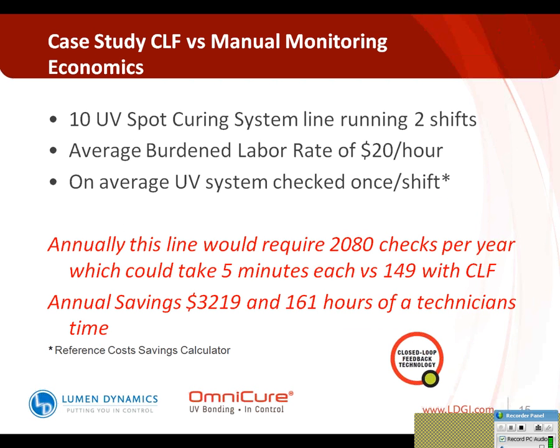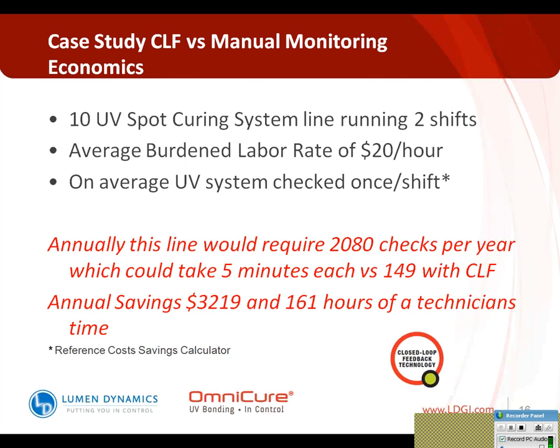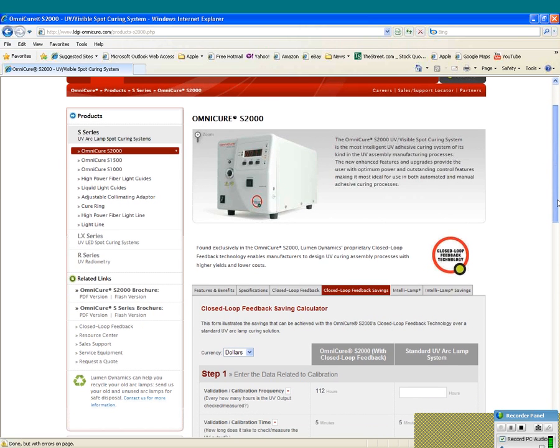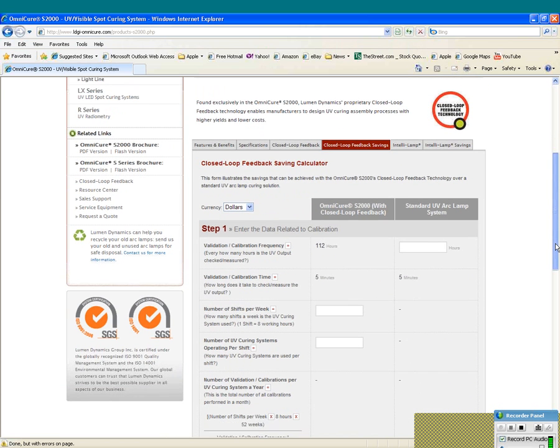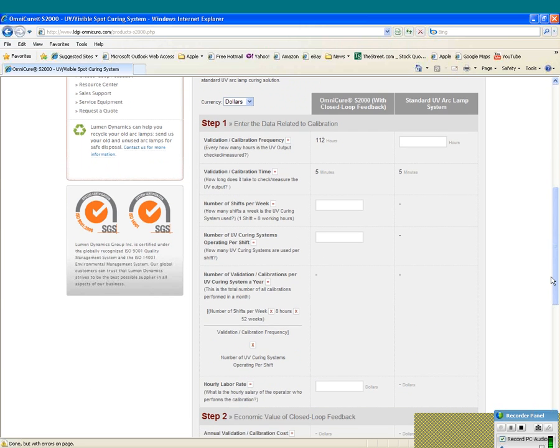So what I wanted to do is run a little calculation just to show you some of the potential savings that you can have with this calculator. The calculator here compares an S2000 system with a standard system that would have a manual adjustment. And in that particular system, what we're saying is that the system will maintain that output within plus or minus 5% for 112 hours. The system will maintain that output.